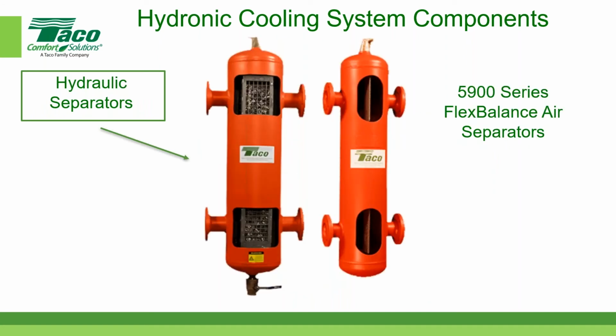Now we get into hydraulic separators. Hydraulic separators, we have two styles. The one on the right is called a 5900. This guy right here is called a 5900, and this separates the primary circuit from the secondary piping circuit or pumping circuit. And the one on the left is called the 5900 Flex Balance Plus. And the plus means that it has these added Pall rings inside these metal baskets in order to enhance the air removal characteristics of the hydraulic separator.